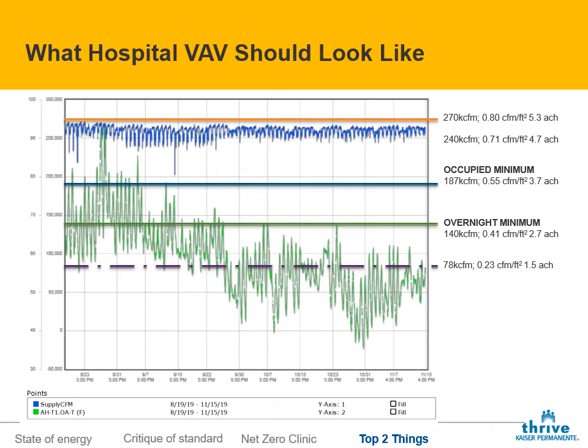The outside air calculations drop off the bottom. You only need about 0.15 to 0.2 CFM per square foot of outside air, so generally it's less than an air change. So it's always going to be the exhaust, at least in the scenarios that I've looked at, that drives your ventilation.